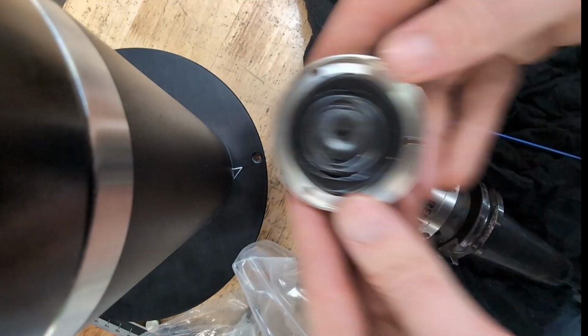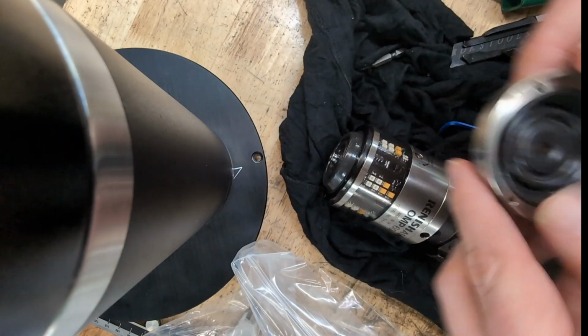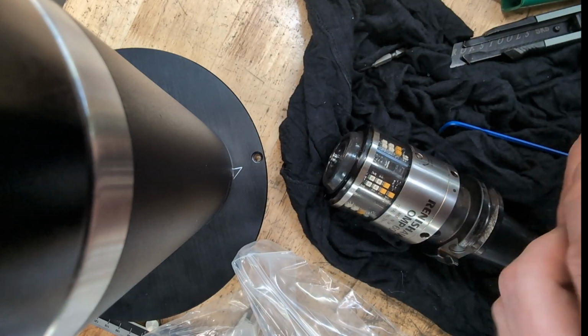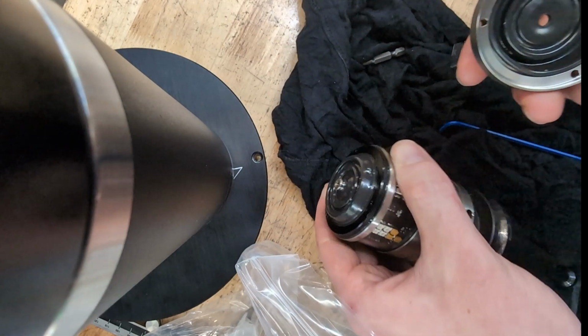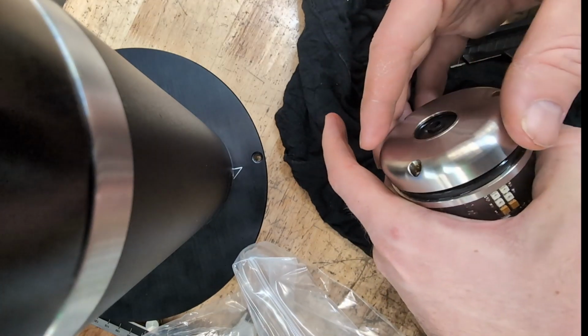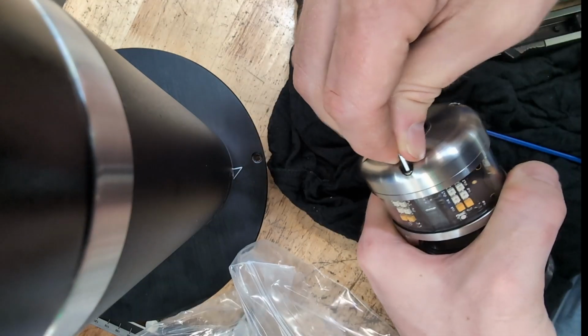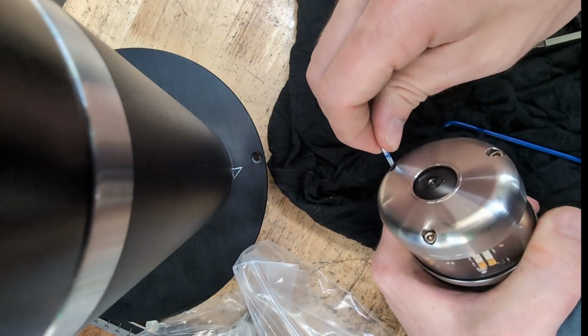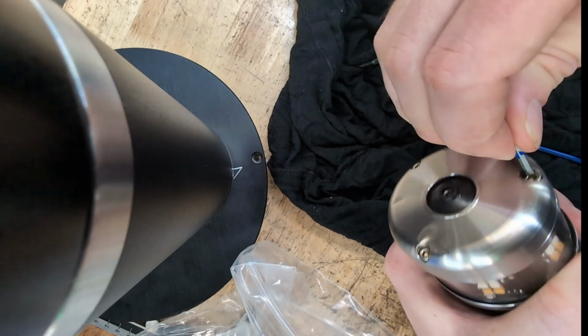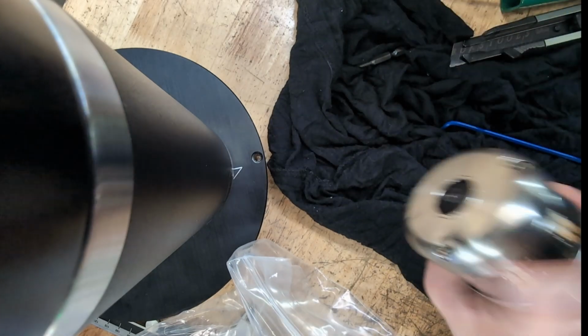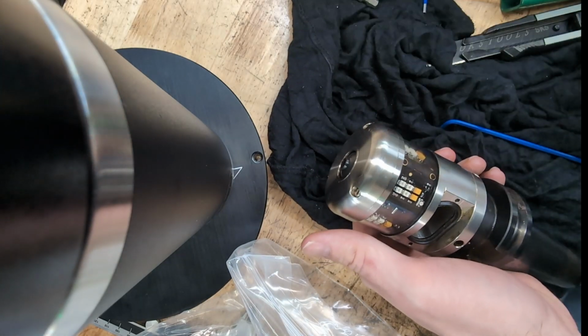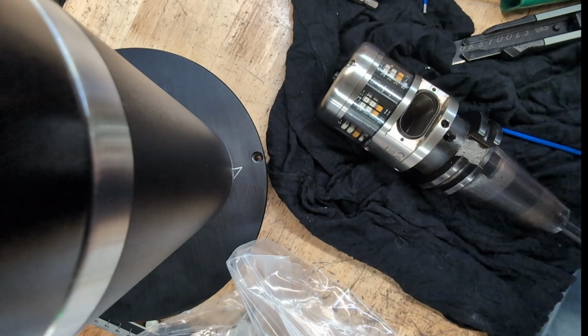The second seal appears to just get pinched between the bottom cap of the probe housing and the main probe body. I found the easiest way to install this was by placing the seal directly inside the bottom recess of the outer housing first, and then sliding the main probe body down into it. Once the bottom cap is on and secured, reach into the center and push the middle of that secondary seal down firmly over the stylus mount so it clears the threads.